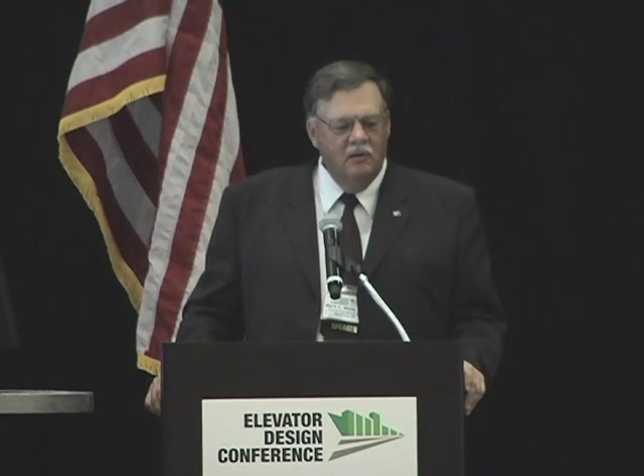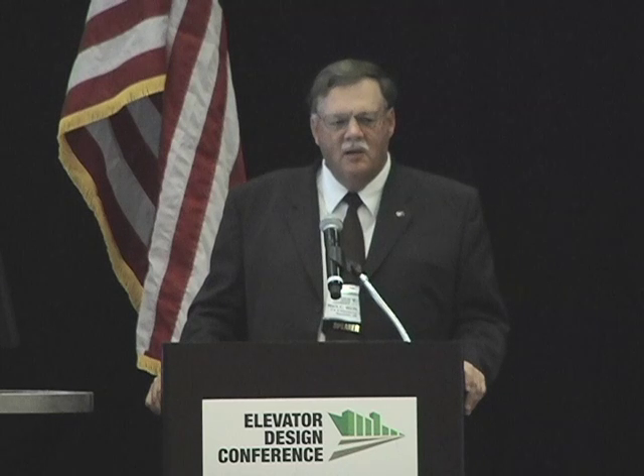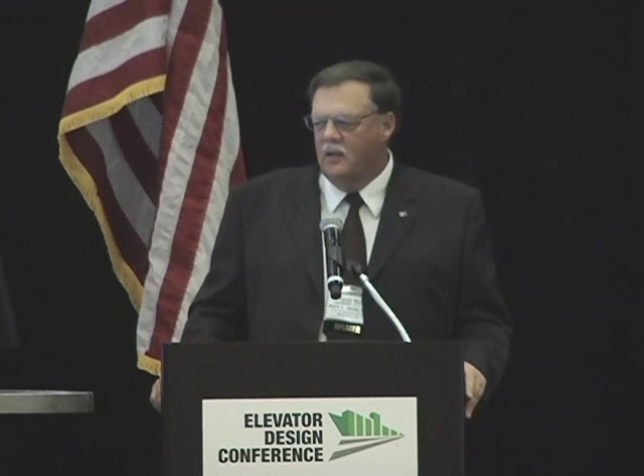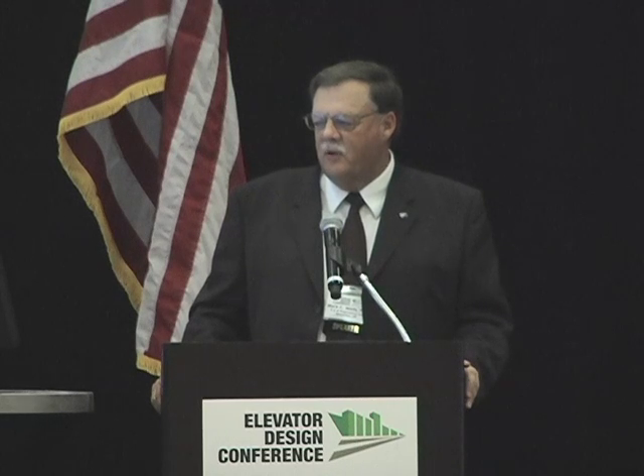We continue to see the cost curves and physical size of VFDs coming down as they're being promulgated throughout the whole electrical industry. And we see them more and more. There are a lot of applications for them, and they don't cost you an arm and a leg anymore. You do have some other issues with them if you put too many of them on your system, but of course, applications are variable feeders for cleaners. You have variable speed feeders for blending applications, for different product flow types, for receiving systems.